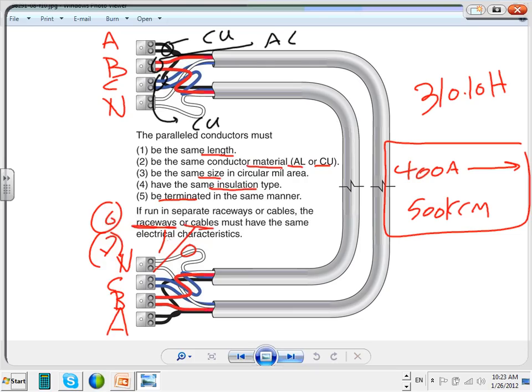Rule 3. Rule 2. Okay, what does it say? Rule 2, be the same conductor material. Are the parallel conductors in A the same material? Yep. Are the B the same material? Yep. Are C the same material? Yep. But the phases don't have to be the same material. The conductors of the same phase have to be the same material. I don't like to even talk about this one because it's a weirdo way of doing it. But yes, you can have phase A all aluminum and phase B and C copper.